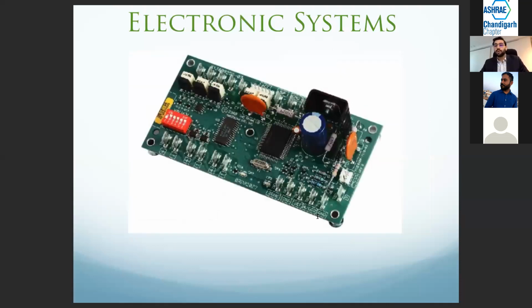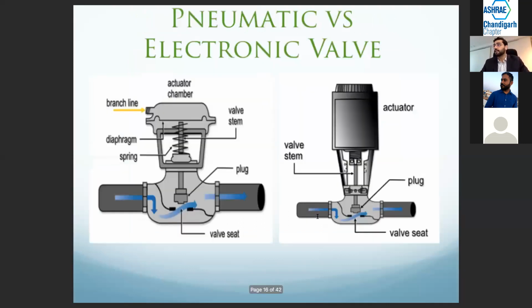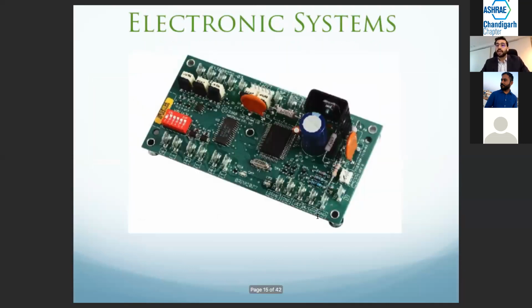Moving on to what we use today, primarily everywhere: electronic systems, sometimes called DDC systems, where everything is electronic. The signals are sent in the form of 0 to 10 volts or 4 to 20 milliamps. Everything kind of looks like this green circuit board, and it's inside a controller casing.